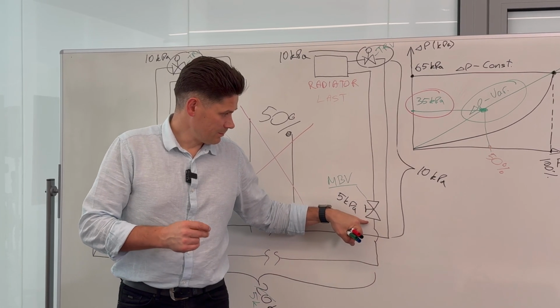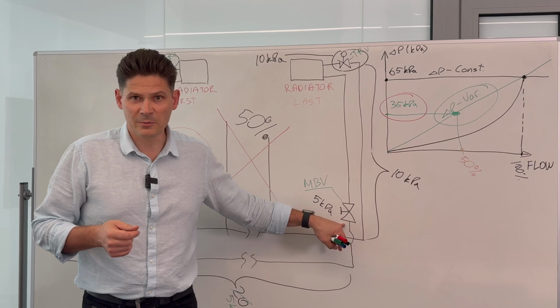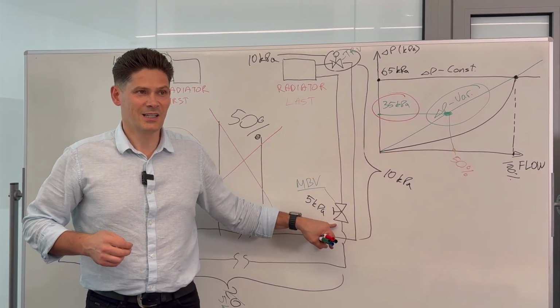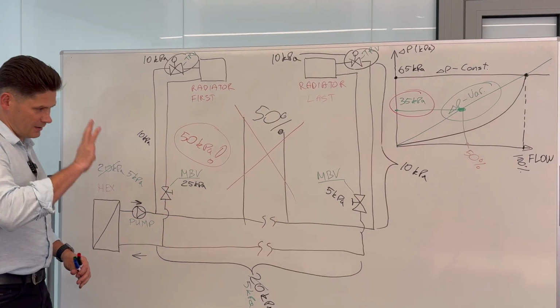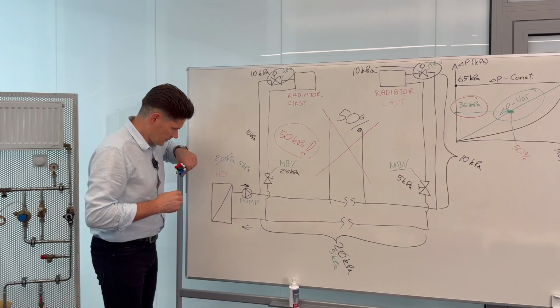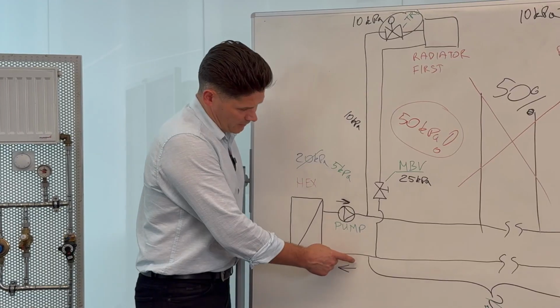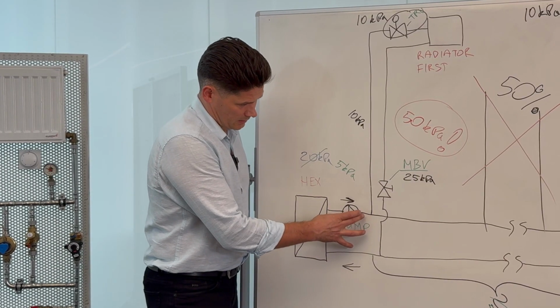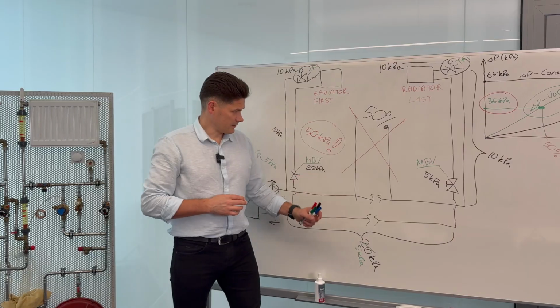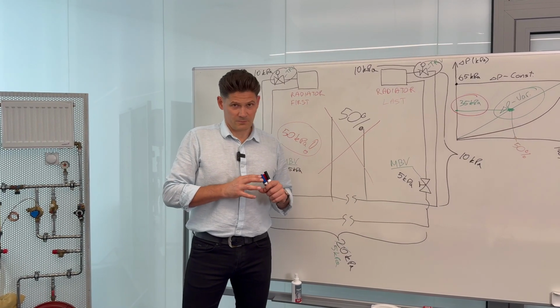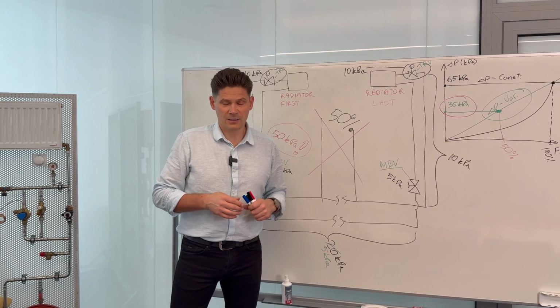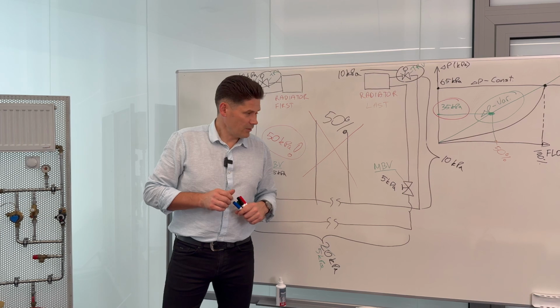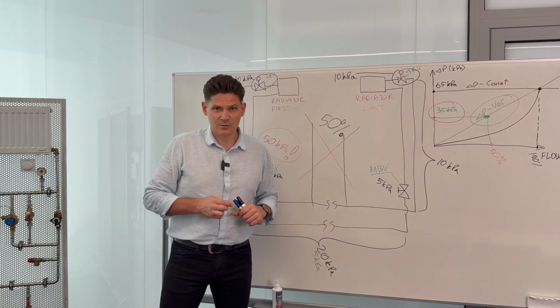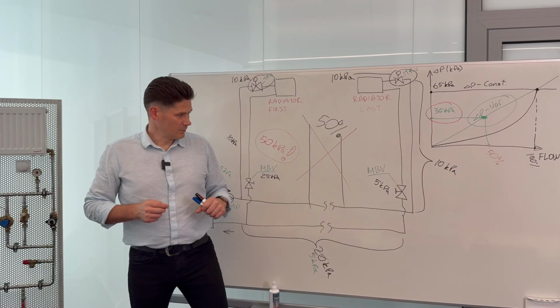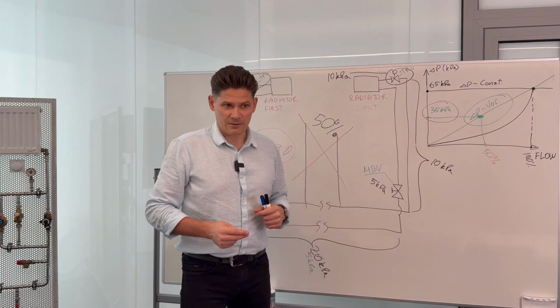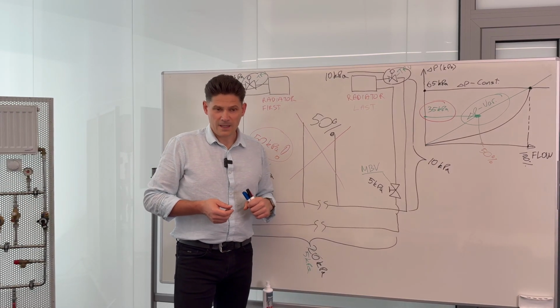And then probably you are asking yourself, so why are manual balancing valves still used? Why are they still being produced? Manual balancing valves, of course, can be used in other applications. We can put a manual balancing valve here to measure the total flow. We can use manual balancing valves somewhere in mixing shunts, also for flow measuring, for flow verification, if you need that. So manual balancing valves will still be produced, but probably not for balancing, not for commissioning, but just for flow measurement, flow verification.